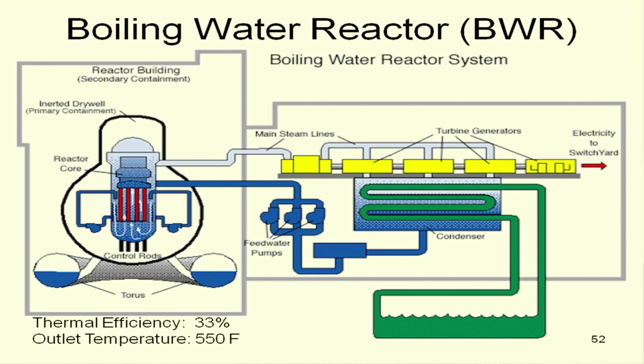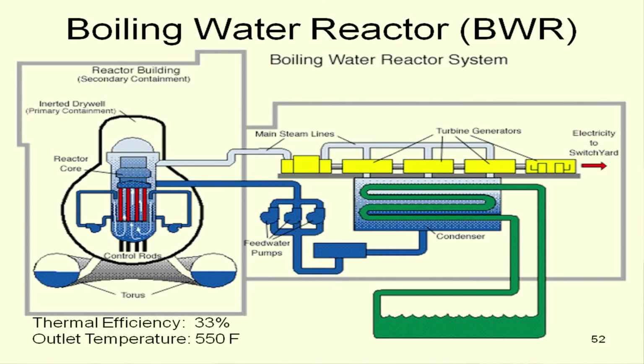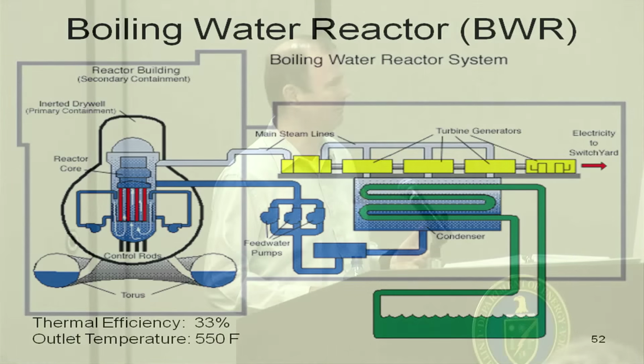And what that means is you're taking water from the reactor core and running it through your turbine system, so there's some degree of radioactivity out there from the corrosion products and all this other junk, whereas in the PWR, that's fairly clean water that goes through the turbine, which is sort of a downside. You take a bit of a temperature hit because of the lower pressure, but on the other hand, you don't have the inefficiencies of the secondary loop. So on balance, they end up with about the same thermal efficiency, and our U.S. fleet is about two-thirds PWR and one-third BWR.